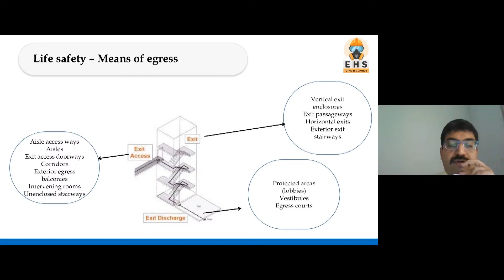The other important point is occupant load. Why is it important? Because the occupant load is different for different types of occupancy. For residential buildings, as per National Building Code, it is 12.5 meter square per person. For commercial, business buildings, it is 10. For mercantile buildings, shops, it is 6. Even for assembly, suppose a theater, it is 0.65. So it depends on occupancy type, and on that basis the other design factors are decided.